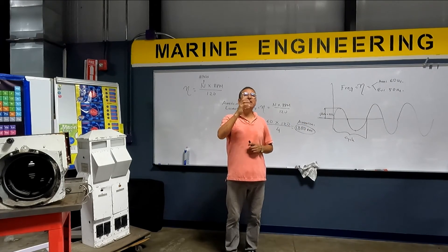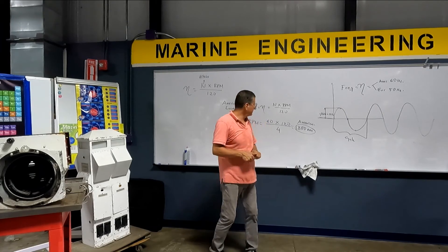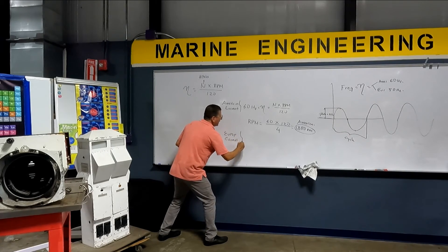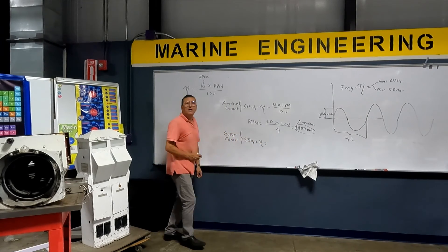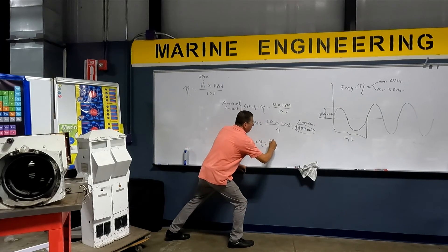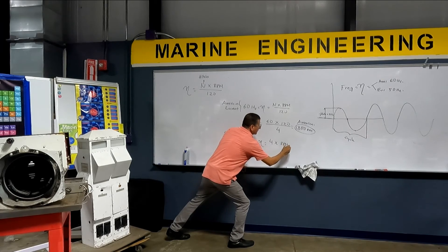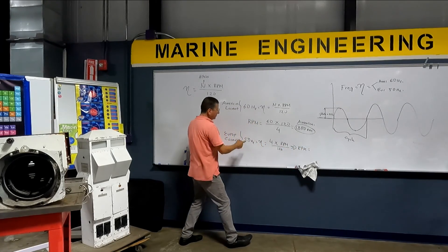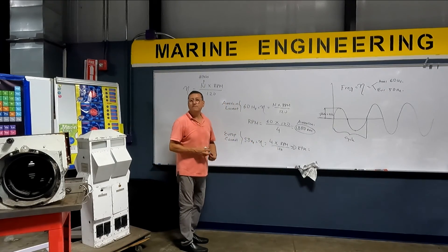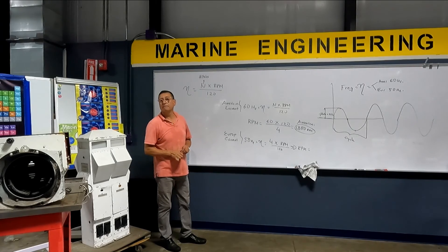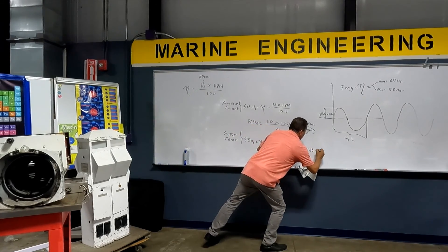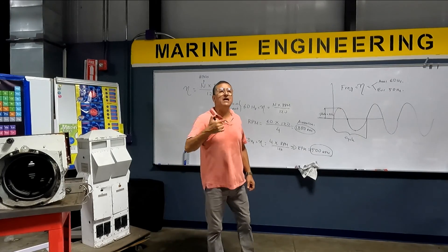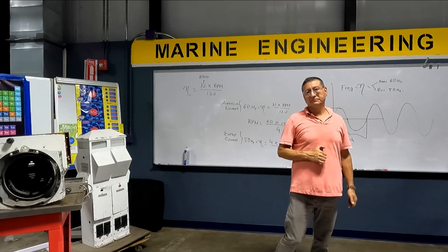Now let's calculate for European power. European power is 50 hertz. Using the same formula: RPMs = (50 × 120) / 4 = 1500 RPMs. So a generator in a European boat runs at 1500 RPMs.